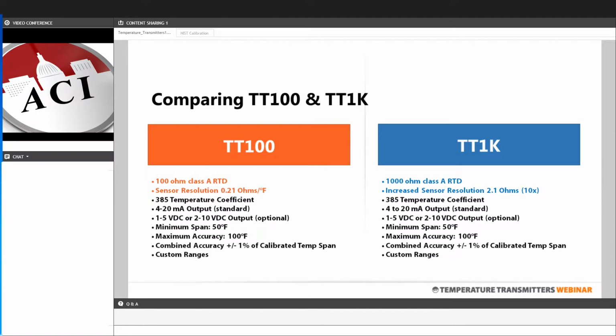These boards are designed to provide the highest level of accuracy in 100 degree F increments. So if you have the choice to pick your temperature span, we'd recommend you doing that in 100 degree increments. So either 0 to 100 degrees F, 0 to 200, minus 50 to plus 50, or any other span in which a 100 degree increment is available. That's going to get you the highest level of accuracy. The minimum span is 50 degrees F for all of our temperature transmitters.